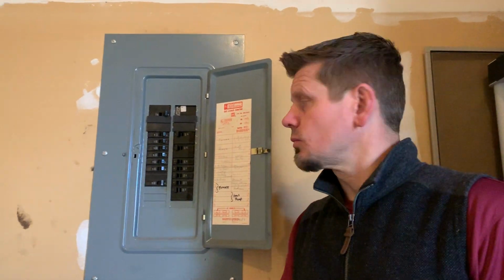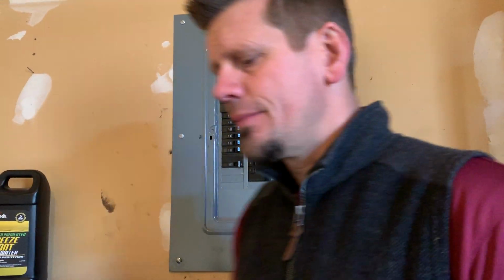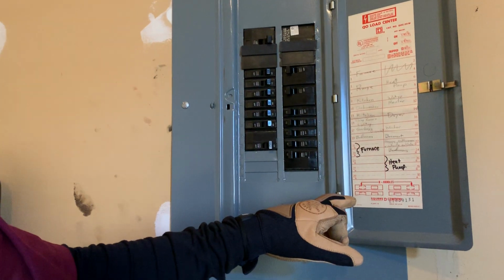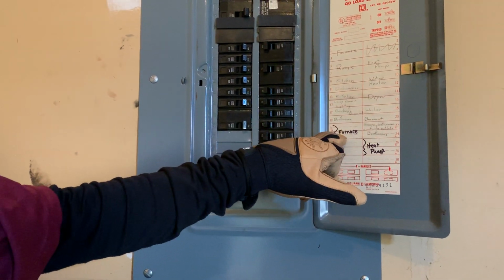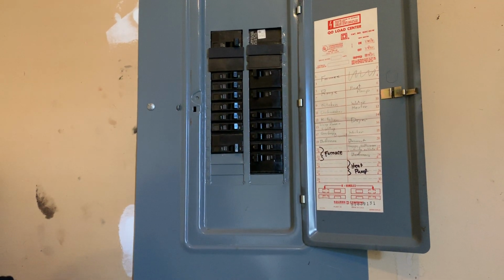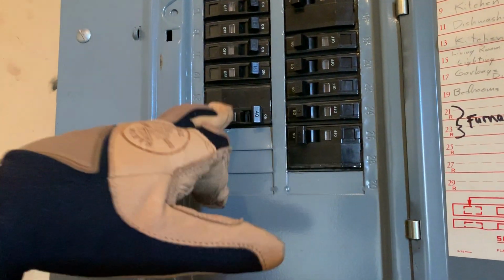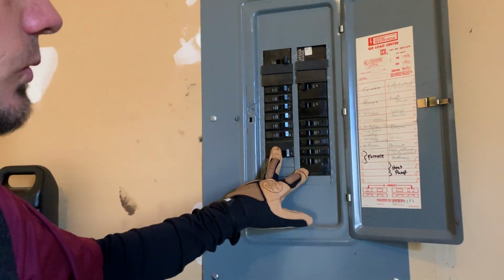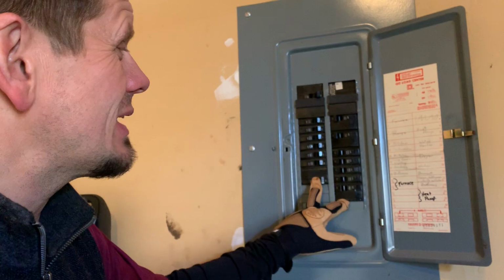But today I want to talk real quickly about this. This system over here in Fort Collins is another area, and they have what we call a heat pump. The property management that brought me over here today was very knowledgeable about this, but basically the furnace is part of this heat pump system, and then the heat pump as well. You're running 40 amps here and 40 amps here. Is it a consistent 80 amps? Not always, but when it's on, it can go up to usually 80% of that breaker's value. So maybe it's running 30 and 30, but that's still 60 amps.